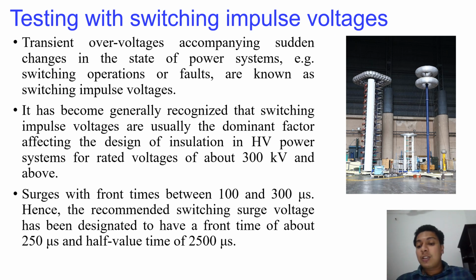But at higher voltage levels, like 300 kV and above, or even 500 or 765 kV, we concentrate more on switching impulse tests than lightning impulse tests, because the switching overvoltage will be huge even compared to the lightning overvoltage effect. So that difference is there.